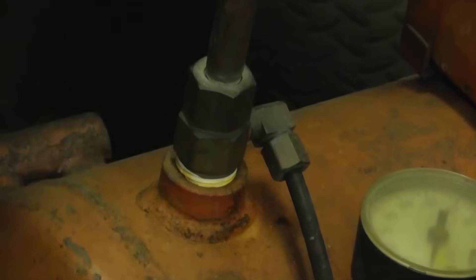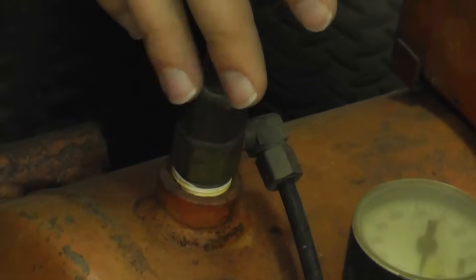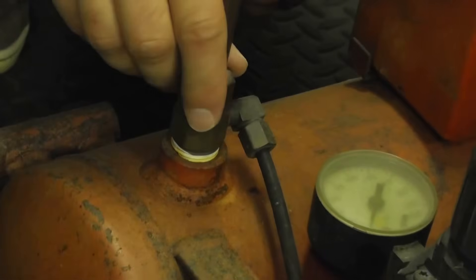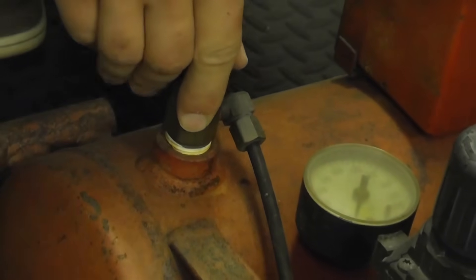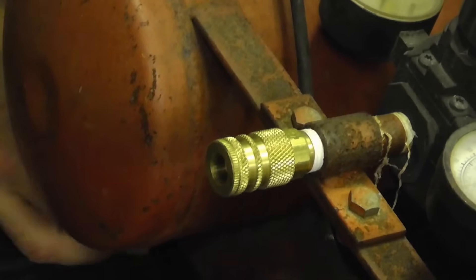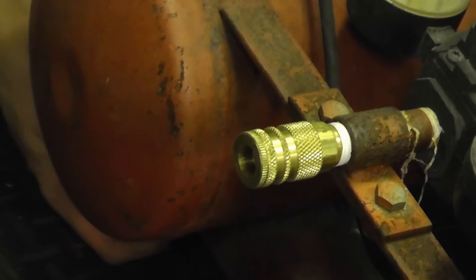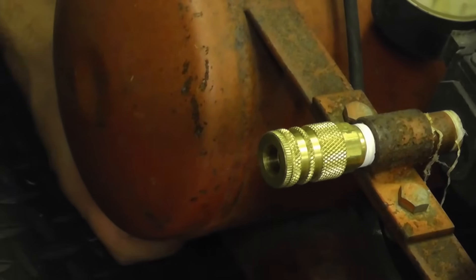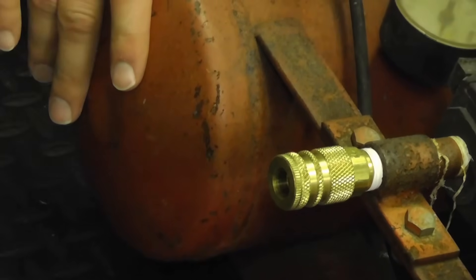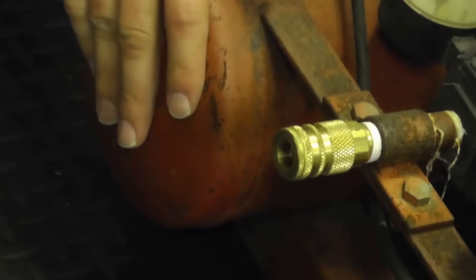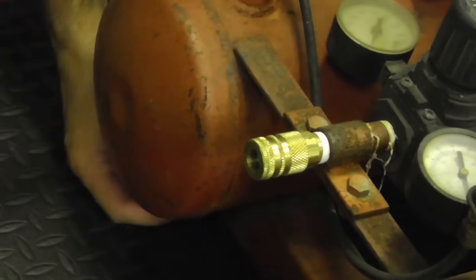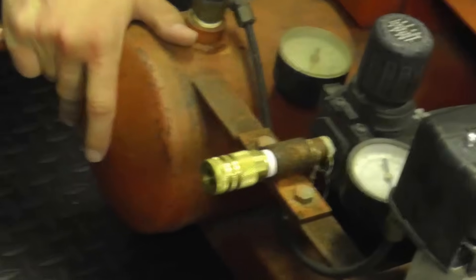That causes all kinds of problems. It's a very common part to replace. Now, drain your tanks. That will keep your check valve also from going bad as well. If you drain your tanks, the drain cocks here in the bottom of your tank, just a simple knurl or wingnut valve, after every extended use, I would recommend draining the tanks because if not, they can build up moisture and it will rust through. So keep the tanks nice and dry by draining your tanks after every extended use.